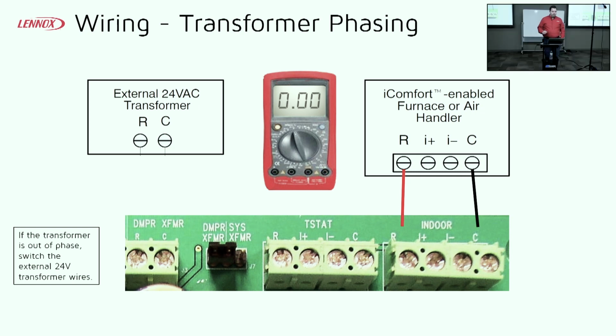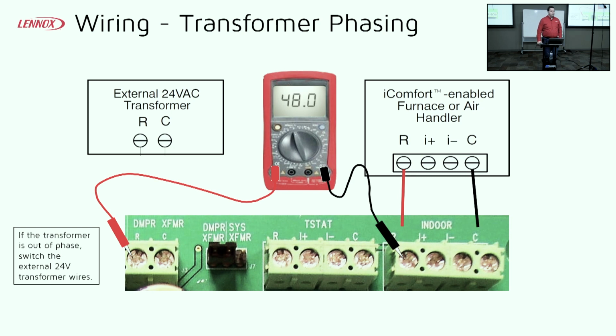Transformer phasing here is very important. So one thing that you'll look at whenever you tie the system in and start it up, this is something you all want to do on startup, is check the R from where your damper transformer ties in to the R where your indoor unit ties in. So you're going R to R there. If everything is in phase, you should have 0 volts, or maybe 1 or 2 volts. Very low single digits. If we're out of phase, then you'll see 48 or 50 volts there. And at that point, all you have to do is swap your plus and minus wire there. Or rather your R and C coming from your damper transformer.